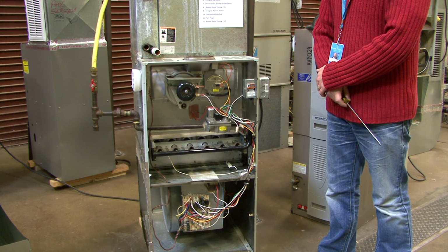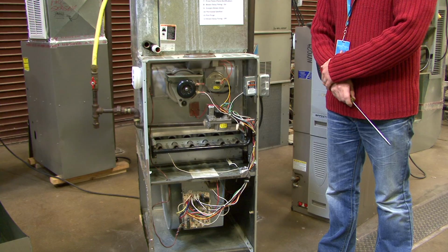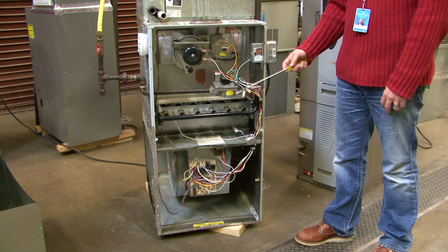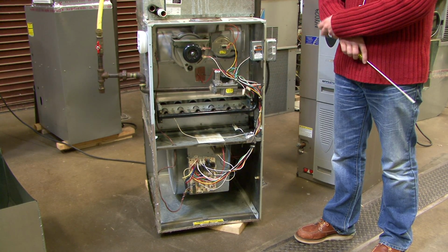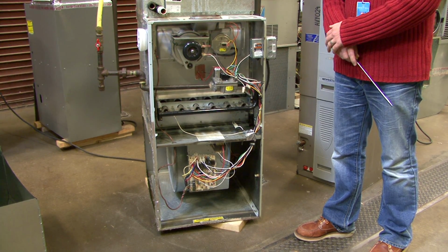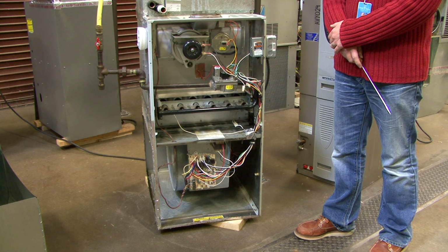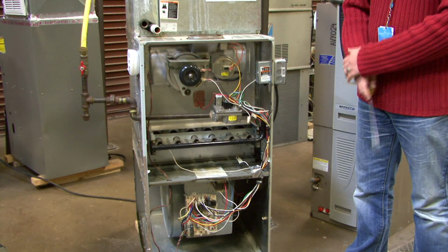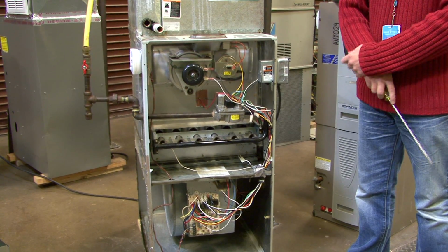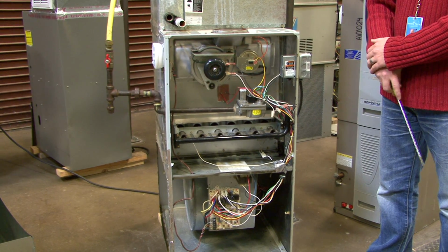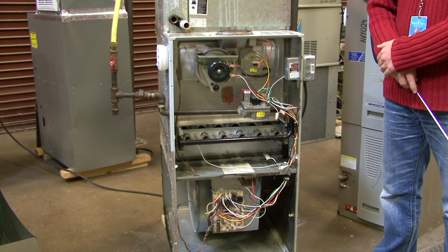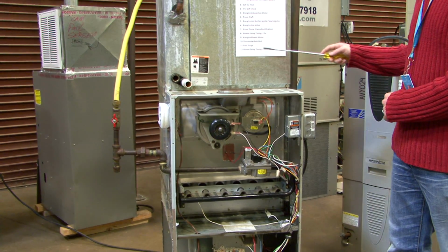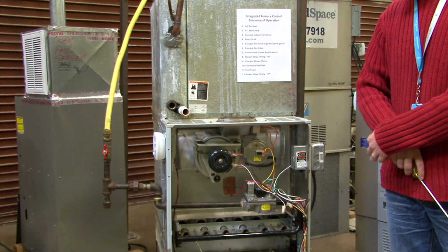After we've proven our flame, we have what's called a blower delay timing to turn it on. So our indoor blower motor is not going to turn on immediately. We want our heat exchanger and the air inside of our heat exchanger to heat up before we start blowing that air into our house. We don't want to have cold drafts going into our customers' and our parents' houses. After that delay timing, we will actually energize our indoor blower motor and blow hot air into the house until our thermostat senses that the room has reached the temperature we've set it at, or our optimum temperature. That's step number 10, our thermostat gets satisfied.